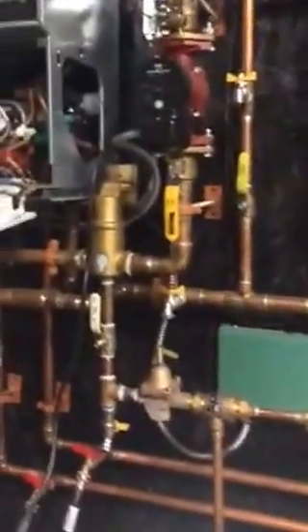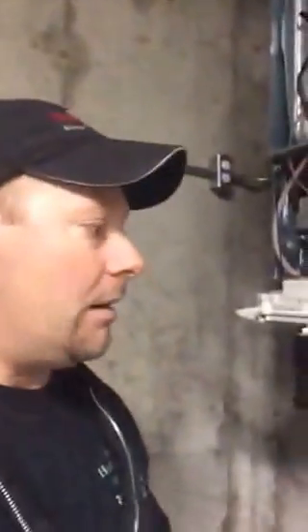So that's what we have to do here to clean that flat plate heat exchanger on the Combi boiler, to prolong the life of it. It saves us from a $300 plus part to exchange out every 3 to 5 years, if that's the case. If you're on hard water, on a well, that's when you're really going to have the problems. City water, not so bad.